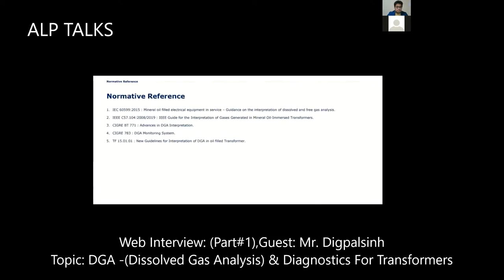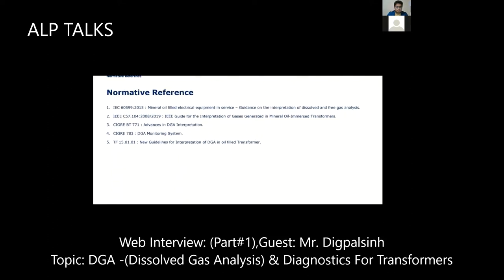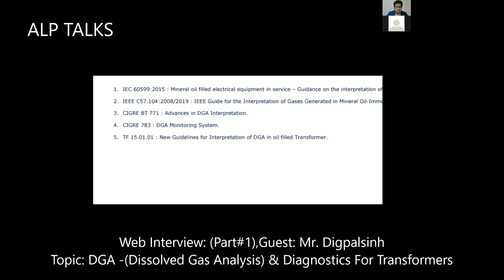Normative references. These are some five to six references which I have used in my software to calculate, interpret or diagnose DGA. First I have used IEC 60599, which is worldwide accepted. This standard gives guidance on the interpretation of dissolved and free gas analysis. Then IEEE C57.104 and CIGRE. I will not take much time on this slide. These are the five main standards you can use in any transformer DGA. The last one, actually, you can say is superseded.